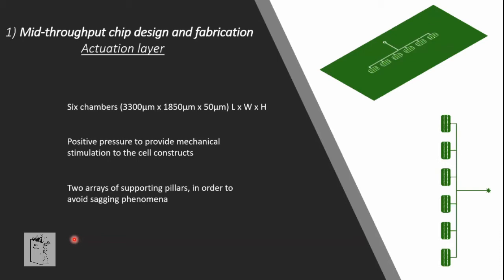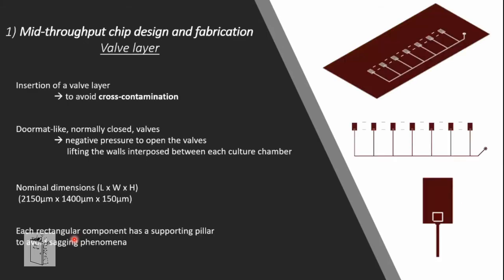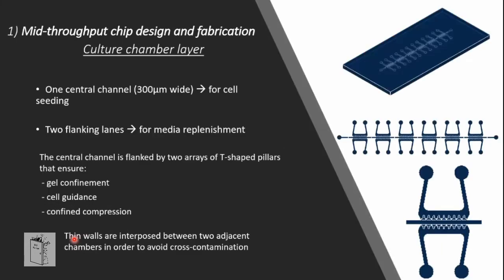Describing each layer in more detail: the actuation layer consists of six different chambers where positive pressure is applied to exert mechanical stimulation on the cell construct. The valve layer avoids cross-contamination by exploiting a system of doormat-like, normally closed valves — applying negative pressure lifts the walls interposed between each culture chamber. The chamber layer also consists of six chambers.